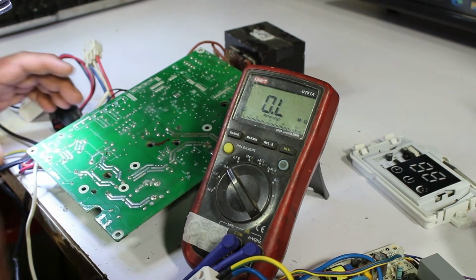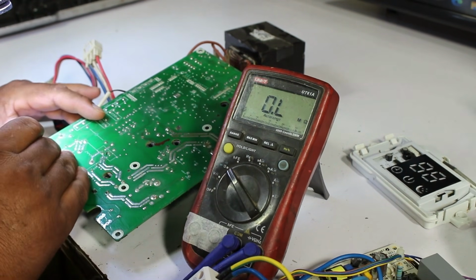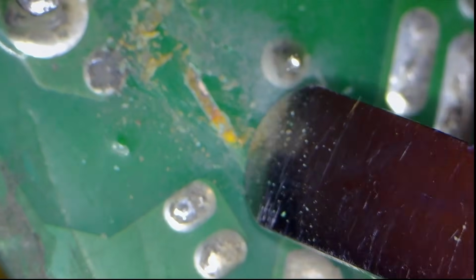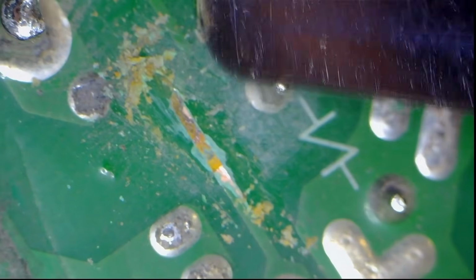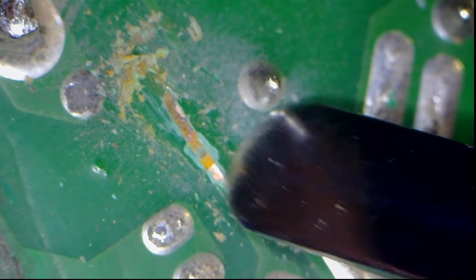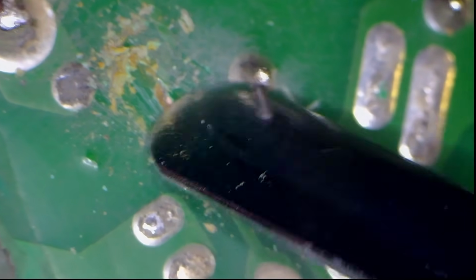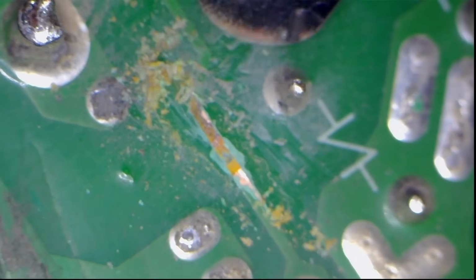Now I'm going to fully clean this trace. I think it's disconnected from here, or there's some issue at this point. It really looks like something has happened here — there's a white mark on this spot. Most likely some chemical, water, or some dirty liquid got on it, and because of that, this trace has been damaged and developed extremely high resistance.